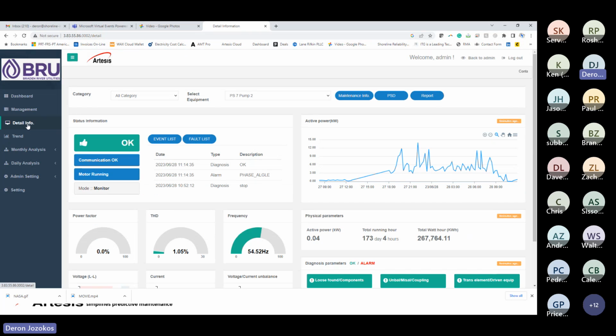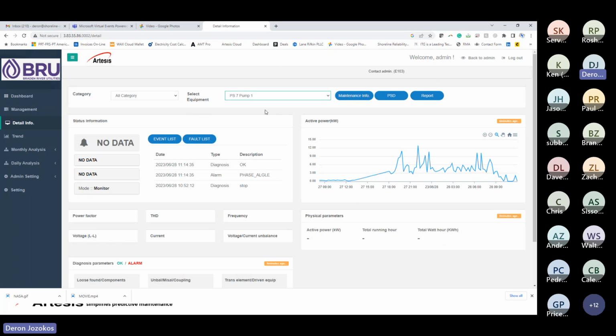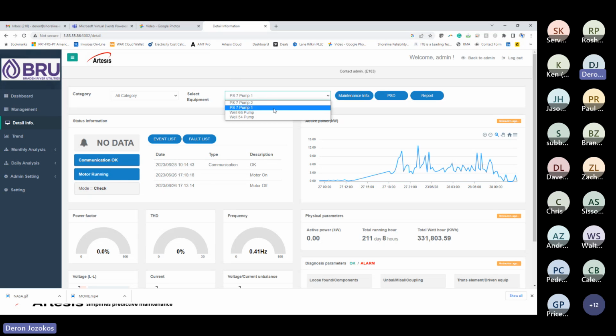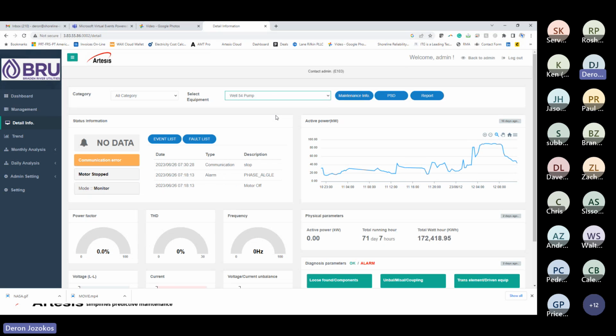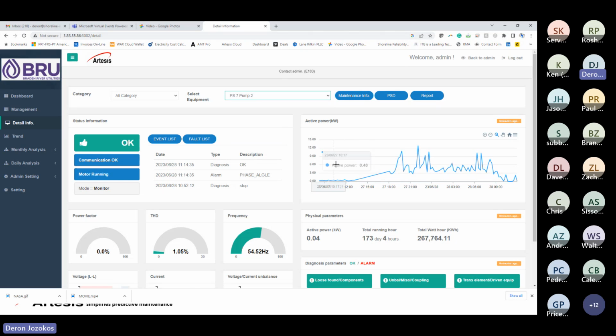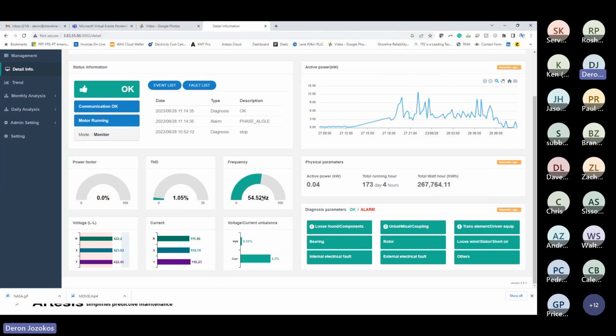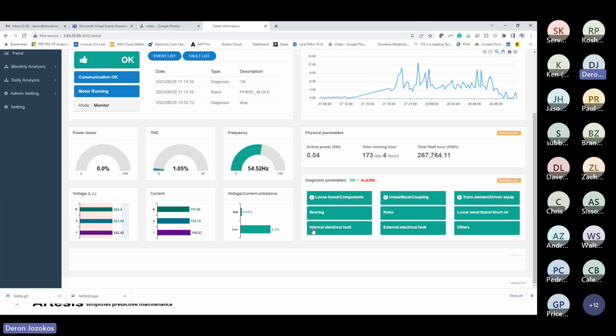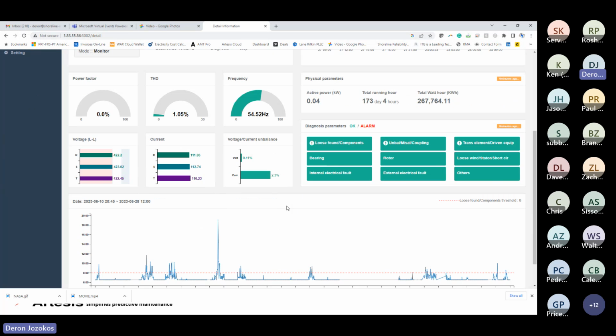Now let's take a look at the detailed info. Now here, we get a quick status of our machinery. You can break this into categories, cooling towers, feed pumps, those types of things. Drop down box of all your machinery. Let's see if there's anything else running here. Active power, all of your electrical parameters here, anything that's in caution will show up with this exclamation point. That's basically something that breached in the past few days. You can see here we breached the threshold the last few days. And then if it stays in alarm, this whole box will turn red.